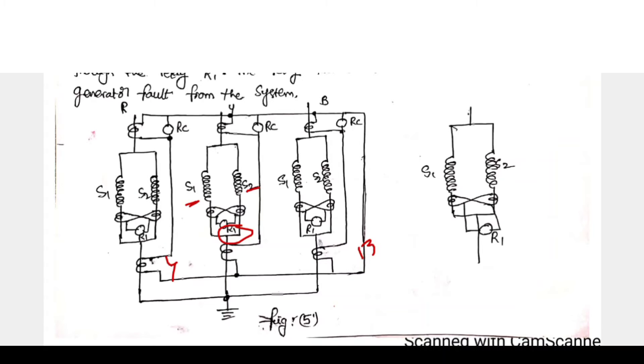If the number of coils, multi-turn coils, we can use inter-turn fault protection. Merz Price circulating current scheme protects against phase-to-ground and phase-to-phase faults.